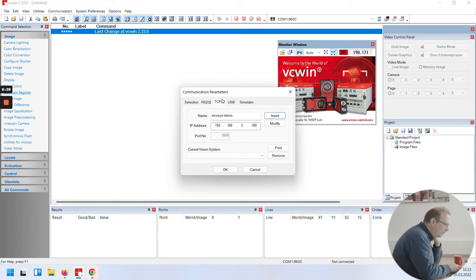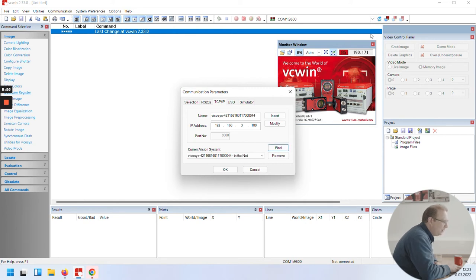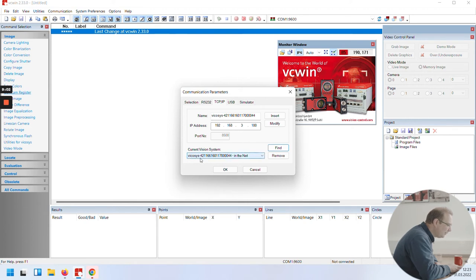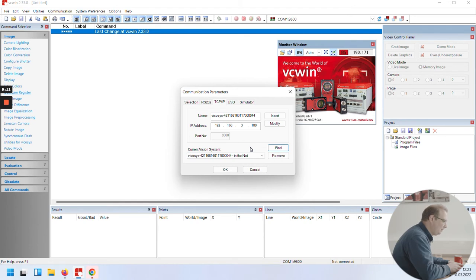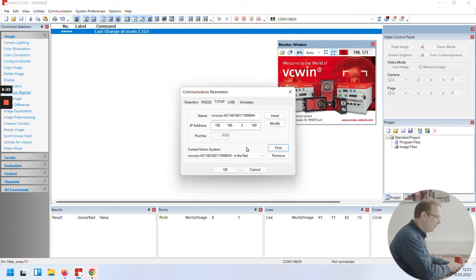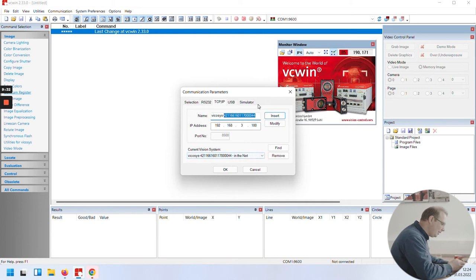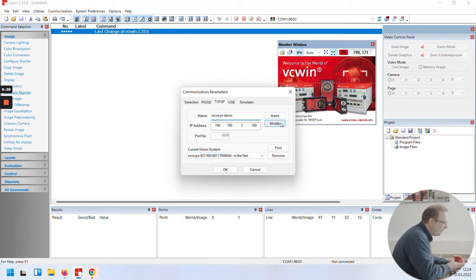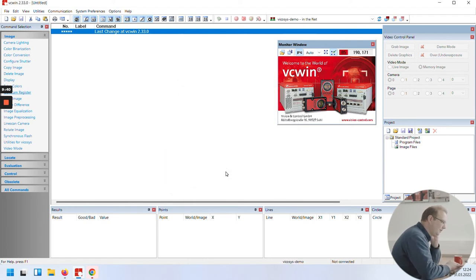You can configure your network settings here in this TCP IP dialog. The most convenient way to do something is here to select this Find button. This will more or less do the same as the double arrow from the very beginning. And you will see here the found devices with the serial number and the comment in the net. That's a good sign that we can really access it. If that doesn't happen, then please check your network configuration, that your laptop is really able to connect with IPs of the Vicosys. If we want to change this name to a more convenient name, we can select here an entry and give it some new name. Hit modify and then it will change the name in our list. This will be stored for next time.